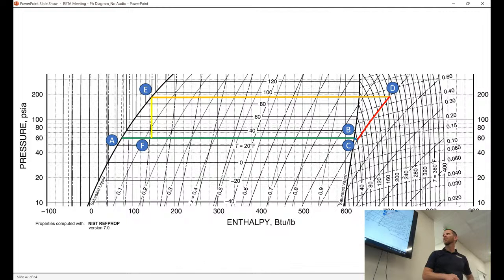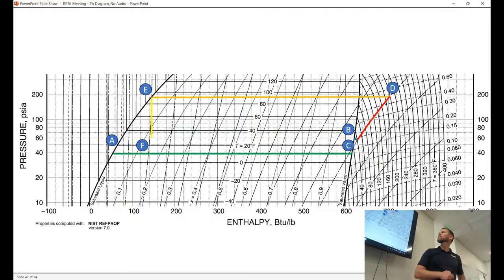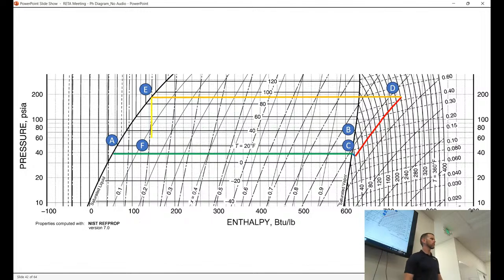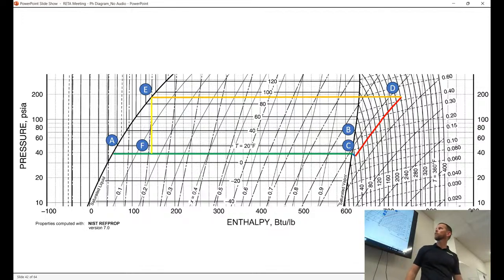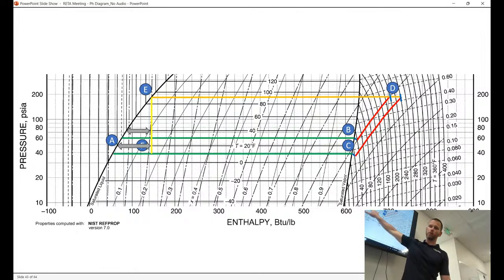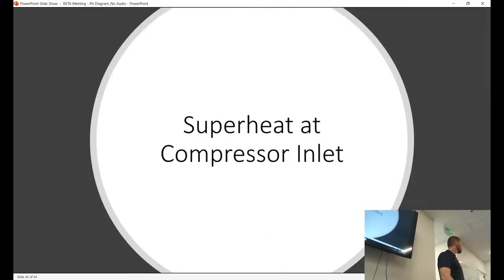Now let's decrease our evaporator pressure — we lowered it down to looks like 10 degrees. Keeping this as a single-stage system, that threw us way out past 240 degrees discharge temperature, which is getting to be almost unacceptable. This is leading to something — we're going to show what a two-stage system would look like. We also have more flash gas. So you could say: by increasing compression ratio — which visually is the distance between the two pressure lines — as that gets bigger, you're going to have higher discharge temperature, more flash gas, and higher power. The same would be true if we raised our condensing pressure.